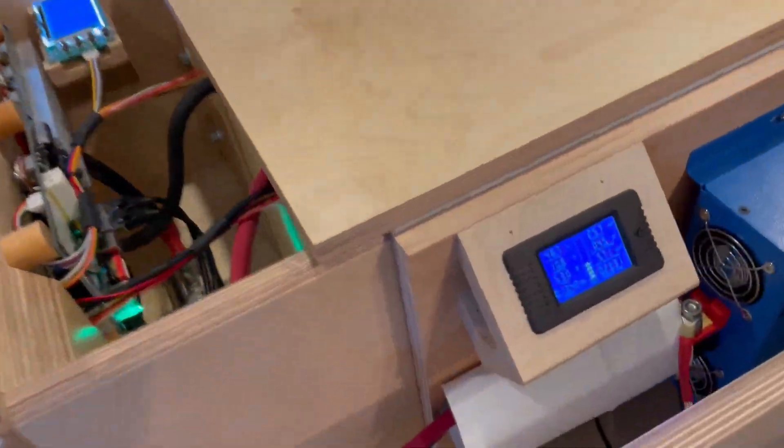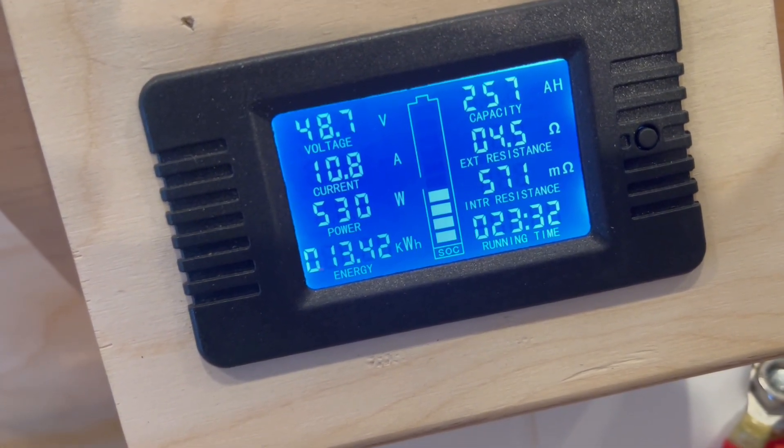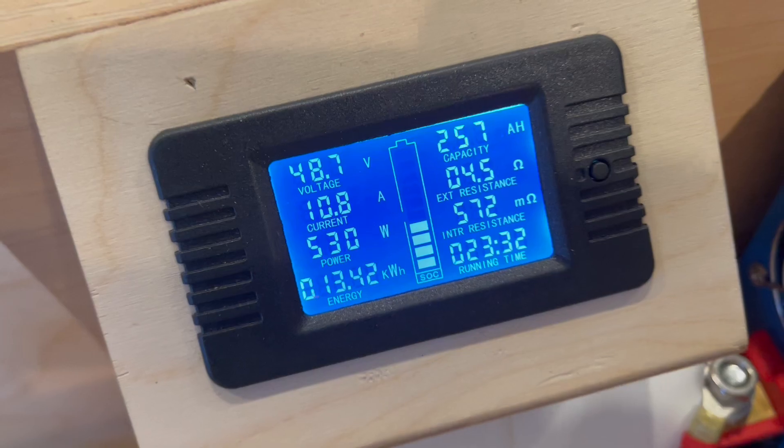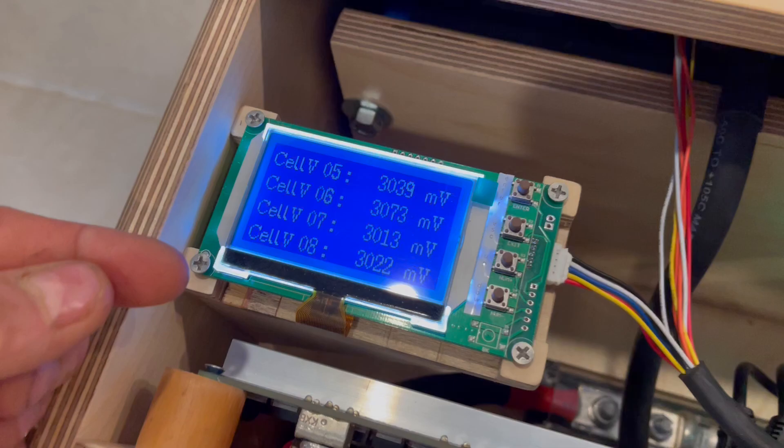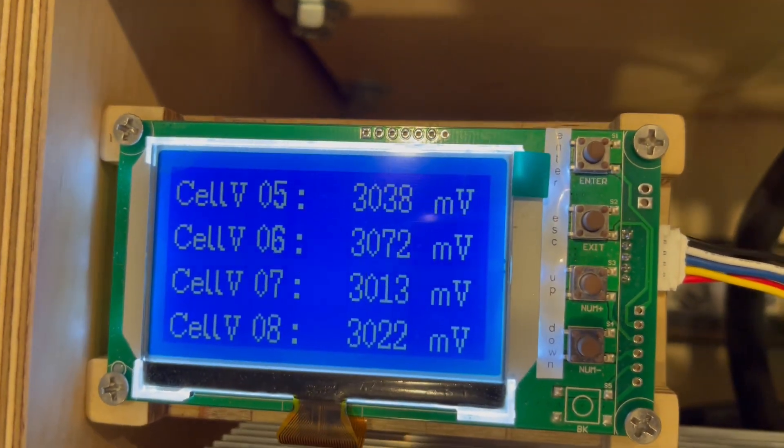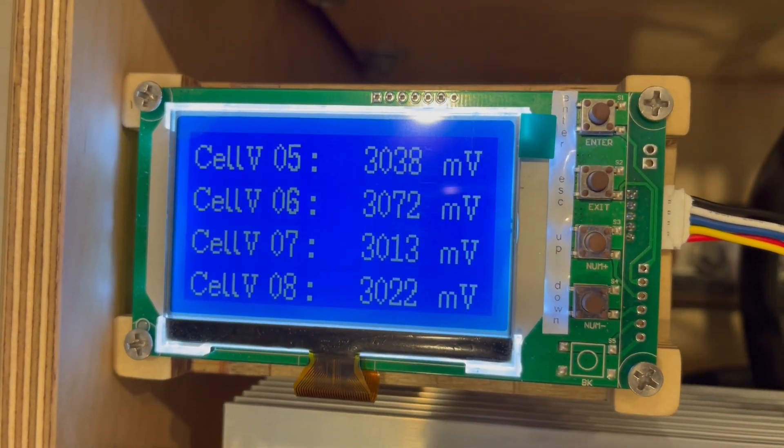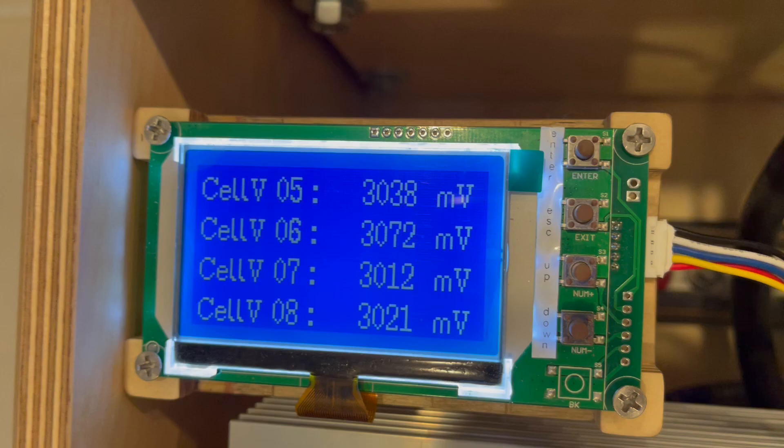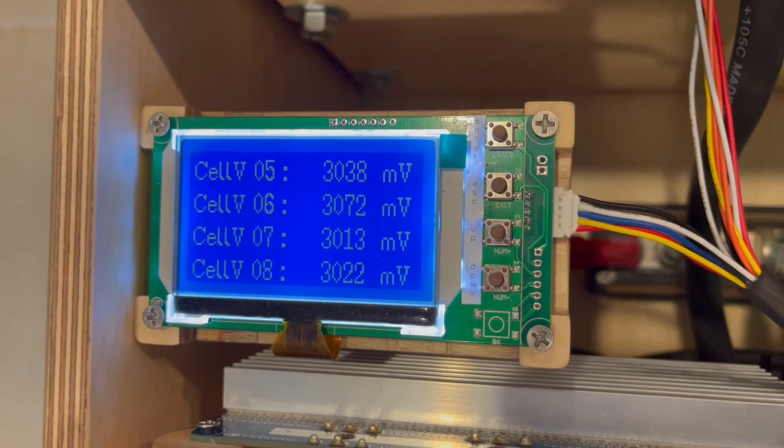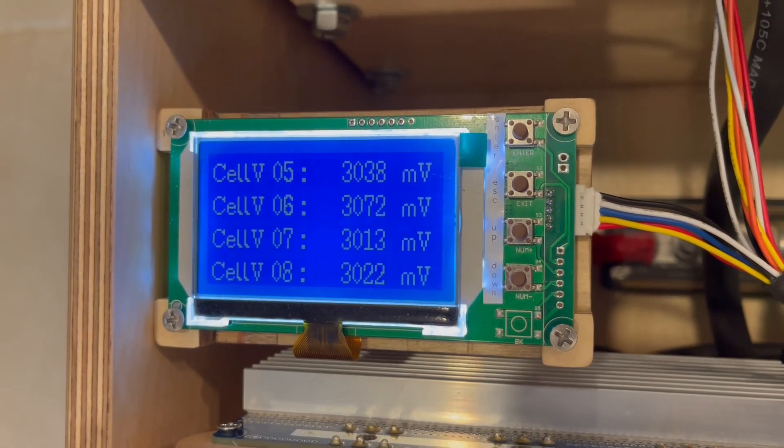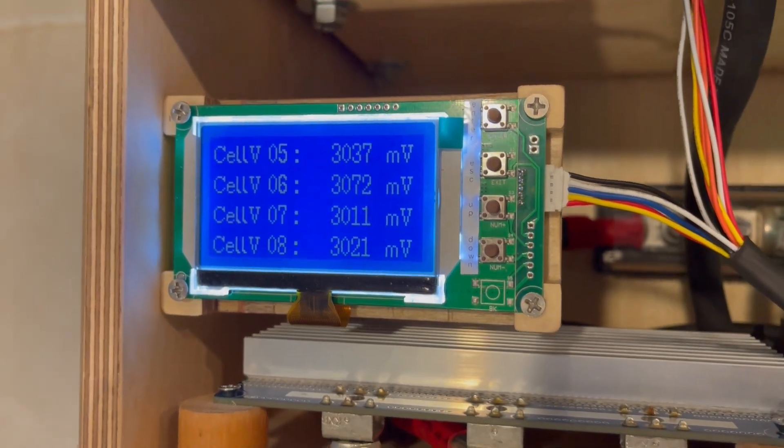So I have so far run 25.7 amp hours out of this battery, and it's been almost 24 hours, and the lowest cell in this battery is at 3.013 volts. This BMS will cut this battery off at 2,800 millivolts, at 2.8 volts. So it's starting to drop rather quickly.